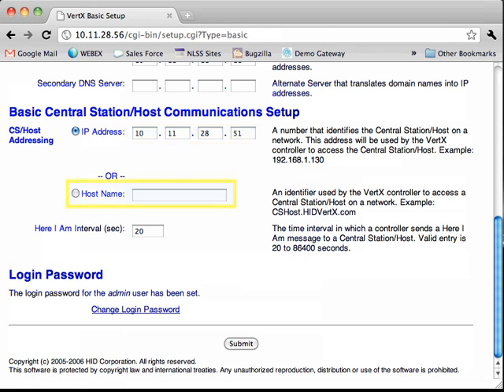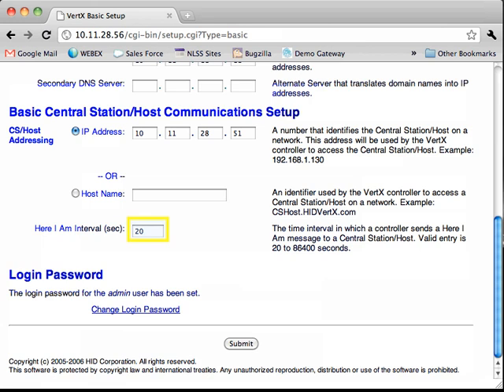Optionally, the host name of the gateway can be used. Finally, we need to assign the Here I am interval. This is the frequency in which the controller will send heartbeat messages to the gateway. These messages are important to ensure that the gateway knows that communication to the controller is still active. Set this value to 20. Click Submit.